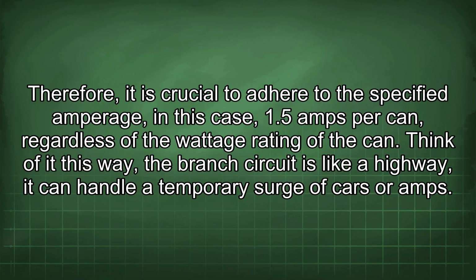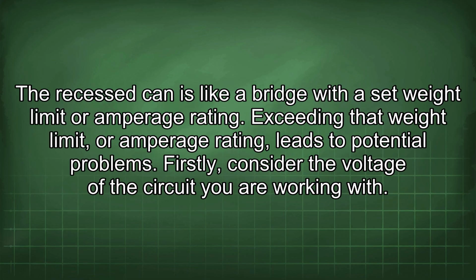Think of it this way: the branch circuit is like a highway. It can handle a temporary surge of cars or amps. The recessed can is like a bridge with a set weight limit or amperage rating. Exceeding that weight limit or amperage rating leads to potential problems.